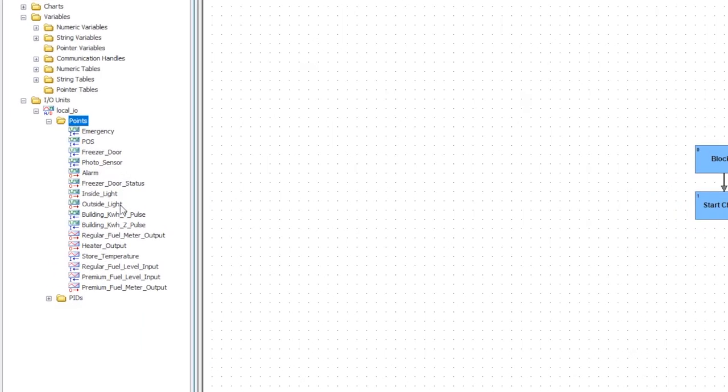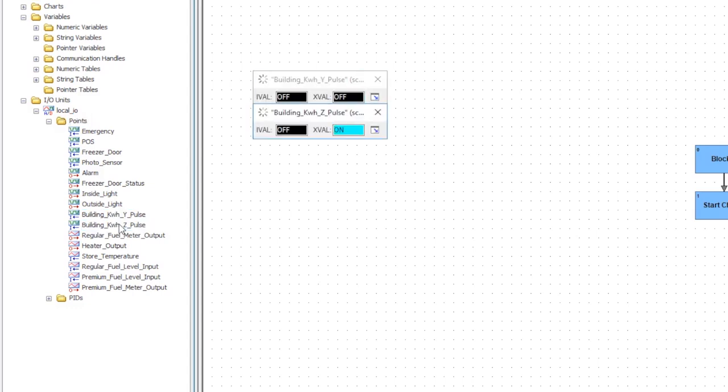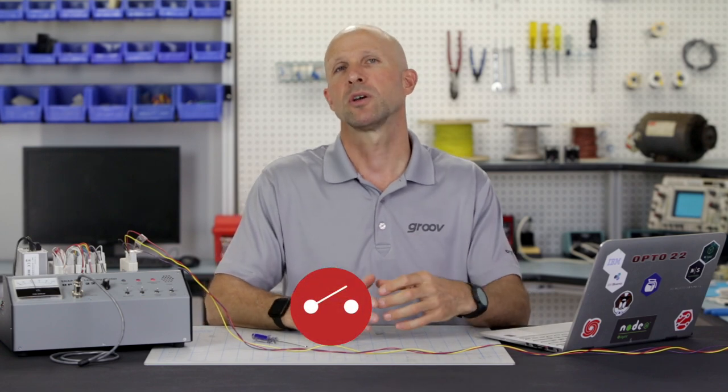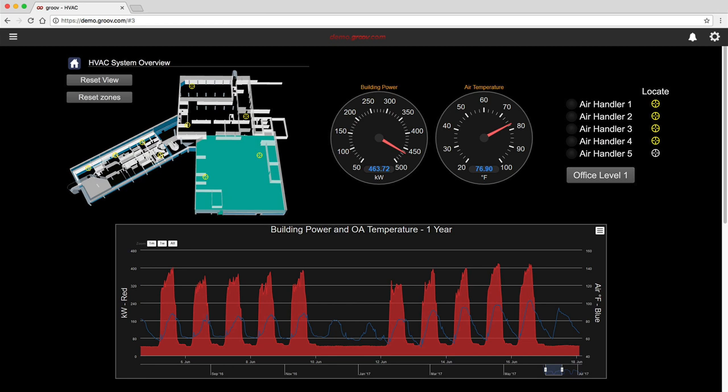Now we can check the two inputs by double-clicking their names in the strategy tree. You can see the power meter pulses arriving in the software — they tick back and forth as each mechanical relay in the power meter switches on and off. At this point you could use PAC Control to measure the time it takes each pulse to arrive and its duration, and from this you can calculate your building power and perhaps sound an alarm or send an email if it goes outside of limits. Or you could log the energy and power use of the facility inside the controller. Here at Opto, once we could see the live energy use of the building, we quickly saw that when air conditioning units turned on at the same time we had a pretty massive power spike — so we changed the building automation code so that only one unit ran at a time and saved a lot of money on our power bill.